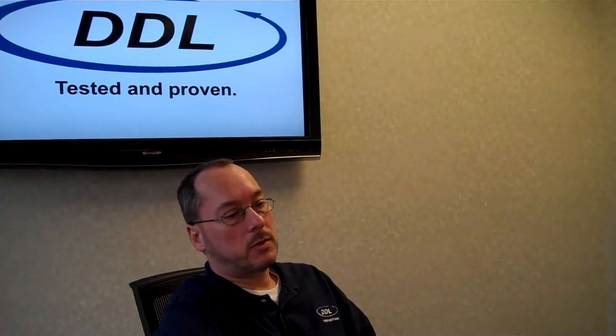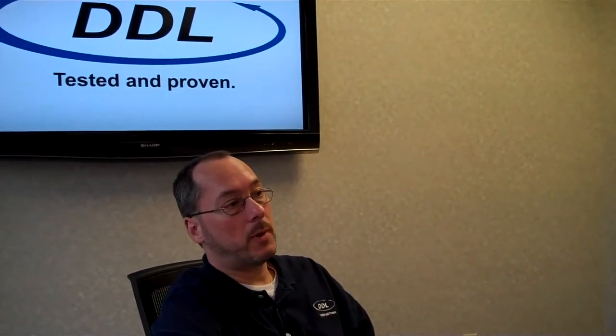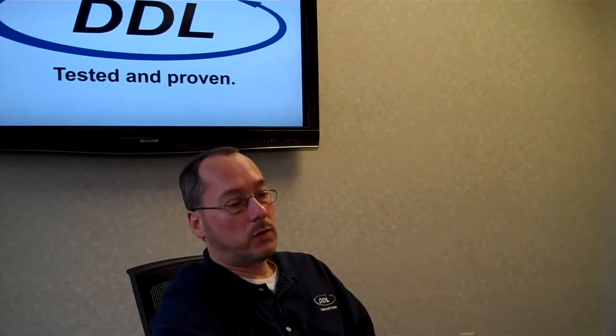To start off, could you please give us a quick overview of the standards for distribution simulation, ISTA 3A and ASTM D7386? Well, thanks Claudia for having me. There are a lot of different test methodologies that medical device manufacturers can utilize on a daily basis to validate their shipping or performance testing of their goods. Two of the most robust test procedures out in the industry right now are ISTA Project 3A as well as ASTM D7386. They both address what basically transpires in a normal distribution environment: drop testing, vibration testing, compression testing.